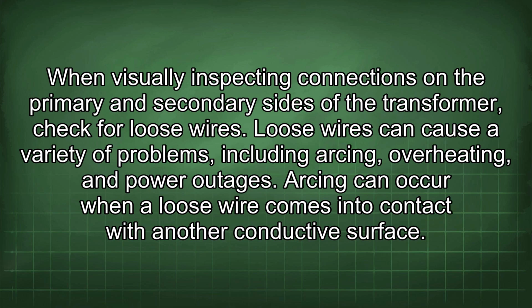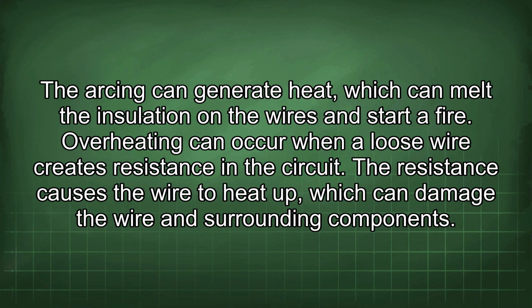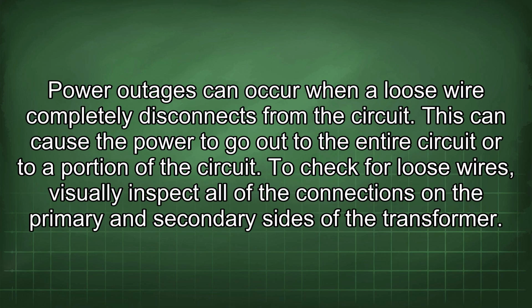Loose wires can cause a variety of problems, including arcing, overheating, and power outages. Arcing can occur when a loose wire comes into contact with another conductive surface. The arcing can generate heat, which can melt the insulation on the wires and start a fire. Overheating can occur when a loose wire creates resistance in the circuit. The resistance causes the wire to heat up, which can damage the wire and surrounding components. Power outages can occur when a loose wire completely disconnects from the circuit. This can cause the power to go out to the entire circuit or to a portion of the circuit.